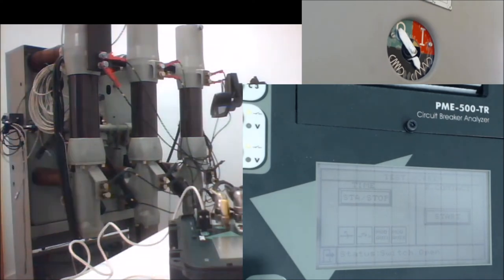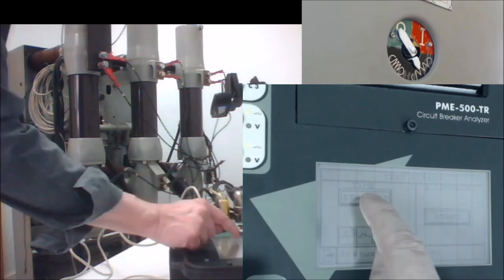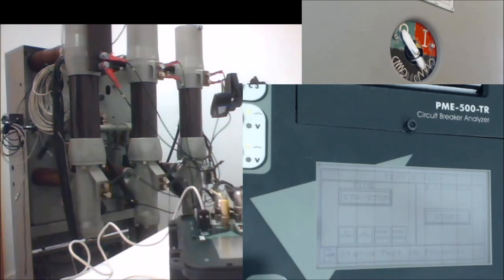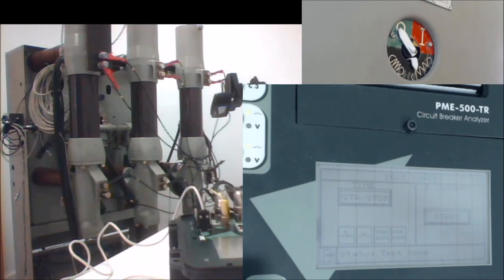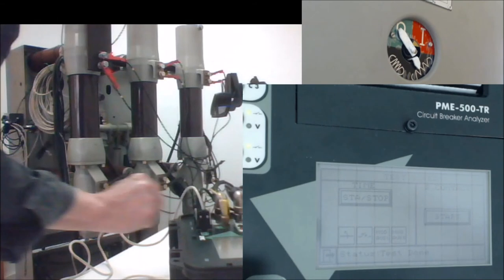We recover the initial open position in order to perform the close-open sequence for the test. We come back to the initial position. Now we press start in order to execute the programmed test — the close-open sequence. When I press here, you will see that it takes approximately one and a half seconds for the unit to initialize the test before the first command is actually issued to the circuit breaker. The breaker is back in the initial open position.